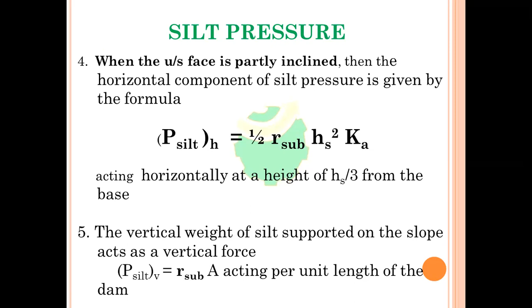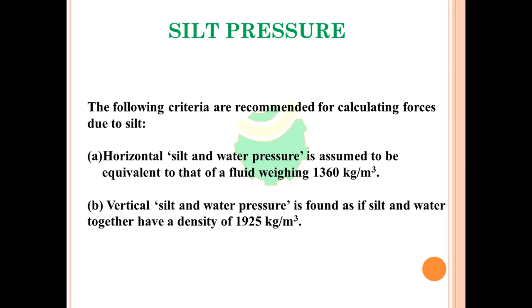Next, the following criteria are recommended for calculating the forces due to silt. First, horizontal silt and water pressure is assumed to be equivalent to a fluid weighing 1360 kg per meter cube. In the vertical direction, silt and water pressure is found as if silt and water together have a density of 1925 kg per meter cube. That means in the horizontal direction, silt and water is 1360 kg per meter cube, and in the vertical direction, the silt and water combined pressure is 1925 kg per meter cube.